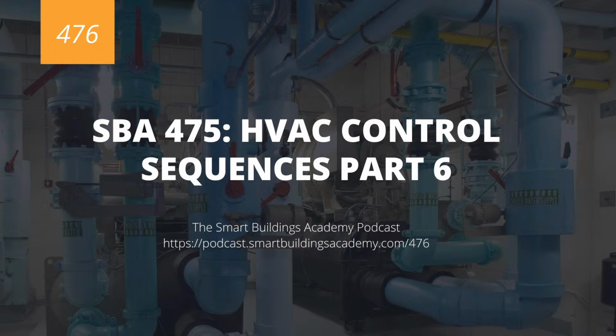What I really want you to take is that on a chiller, there are also two sides of the chiller. You've got the condenser side and you've got the evaporative side, right? So the evaporative side is typically known as the chilled water side of the chiller. And that is where we're chilling the air and chilling the water. And then the condenser side is actually where we're removing that heat, right? So on the evaporator side, we're absorbing heat, and on the condenser side, we're removing and transferring that heat outside, okay?